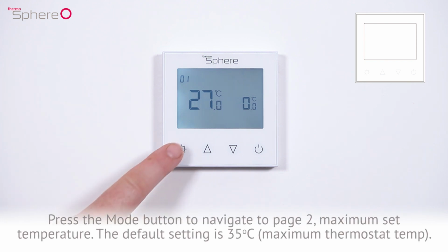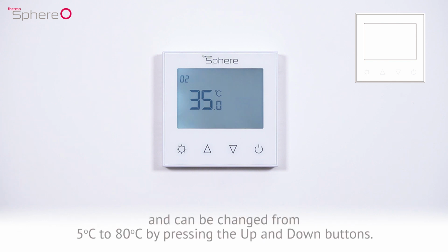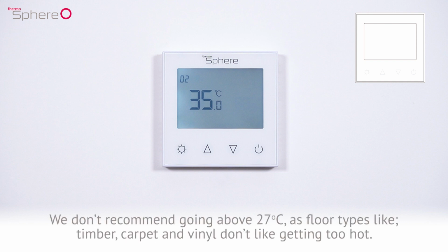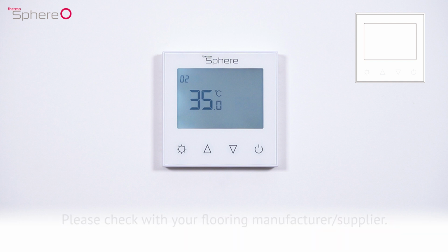The current temperature is also displayed, in our situation 27 degrees Celsius. Press the mode button to navigate to page 2, maximum set temperature. The default setting is 35 degrees Celsius, which is the maximum thermostat temperature, and can be changed from 5 degrees Celsius to 80 degrees Celsius by pressing the up and down buttons. We don't recommend going above 27 degrees Celsius, as floor types like timber, carpet and vinyl don't like getting too hot. Please check with your flooring manufacturer to find out more.